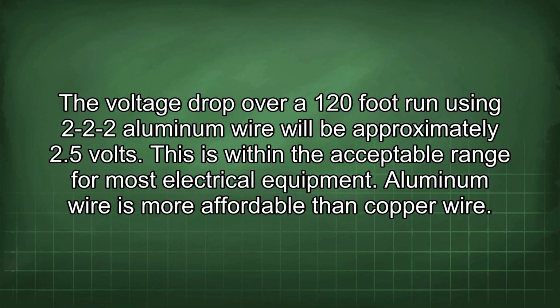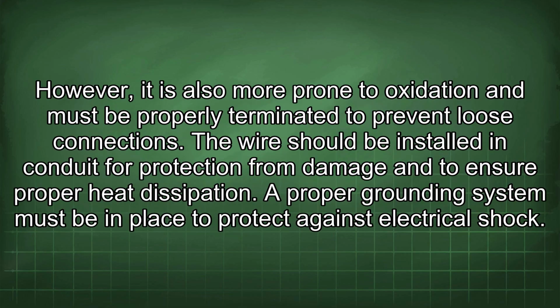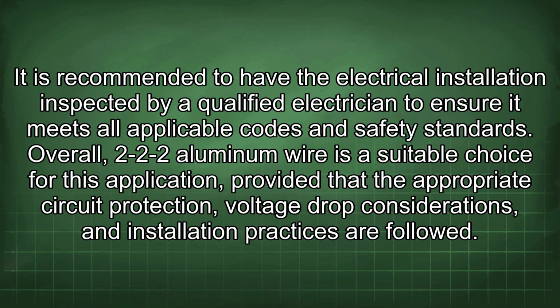Aluminum wire is more affordable than copper wire. However, it is also more prone to oxidation and must be properly terminated to prevent loose connections. The wire should be installed in conduit for protection from damage and to ensure proper heat dissipation. A proper grounding system must be in place to protect against electrical shock. It is recommended to have the electrical installation inspected by a qualified electrician to ensure it meets all applicable codes and safety standards. Overall, 2-2-2 aluminum wire is a suitable choice for this application, provided that the appropriate circuit protection, voltage drop considerations, and installation practices are followed.